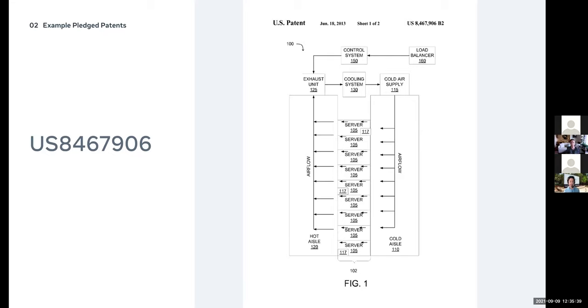For that flow, there's a maximum amount of load you can send to a server that the cooling can handle, based on how much cool air passes across before the temperature starts increasing. So the goal is to maximize server load without increasing temperature for a given pressure differential.